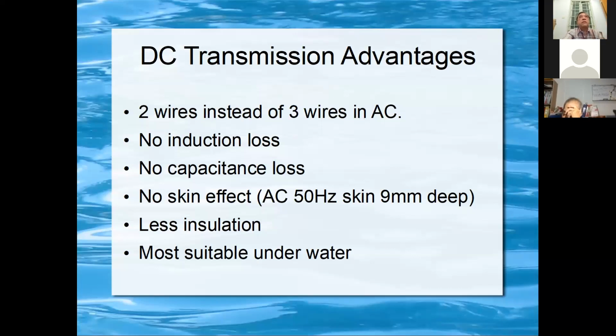So at lower frequency, the skin effect is less apparent. But at 50 hertz, the skin effect is 9 mm. 9 mm is not a lot, because if you count the diameter it's like 18 mm. But the cable is very thick. If your cable is very thick, then 9 mm becomes a lot, already a problem. So you have a limit.